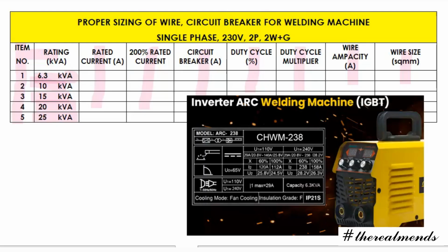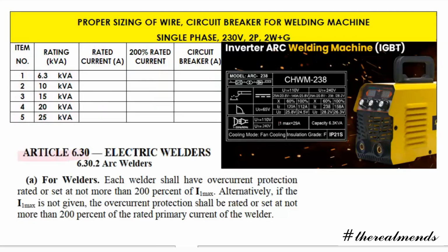So again, itong 6.3 is coming from our sample nameplate. Okay, sample nameplate 6.3. So itong 10 kVA, so assuming na we have itong rating na to. And then to get the rated current, we have PEC, so reference. Refer to PEC article 6.30, electric welders 6.30.2 dun sa arc welders. So each welder shall have overcurrent protection rated or set not more than 200% of Imax.